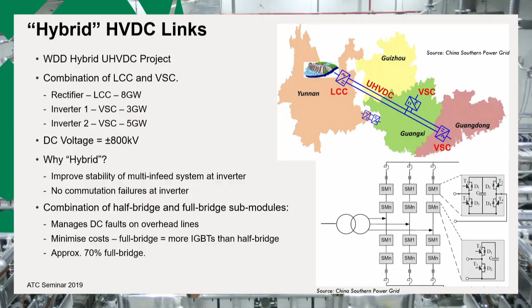Why do you do it? Converters are more susceptible to commutation failures when they're an inverter, so you make the inverters VSC. The LCC is connected to a very strong network, giving you the lower losses and better fault handling capability. So it's using the benefits of both and tackling the disadvantages of both at the same time. Could be the way of the future, who knows? The other new thing about this particular project is it's using a combination of full bridge modules and half bridge.